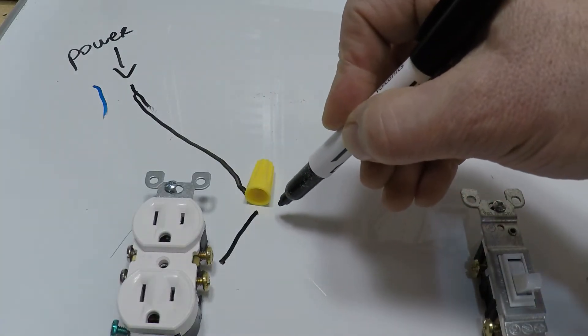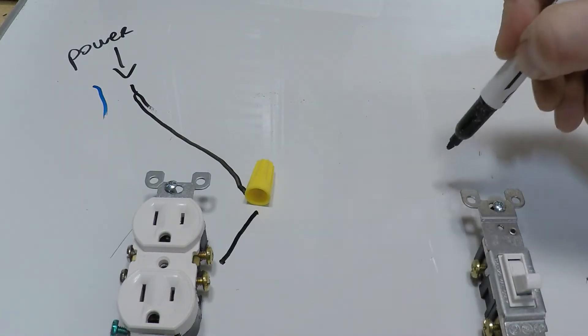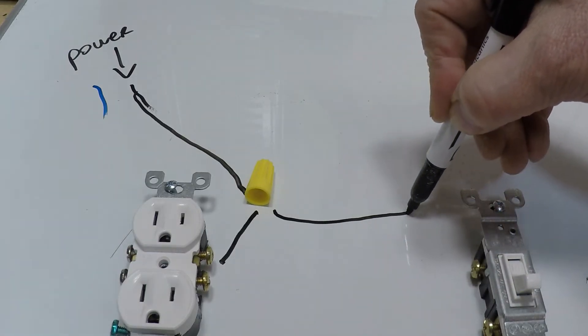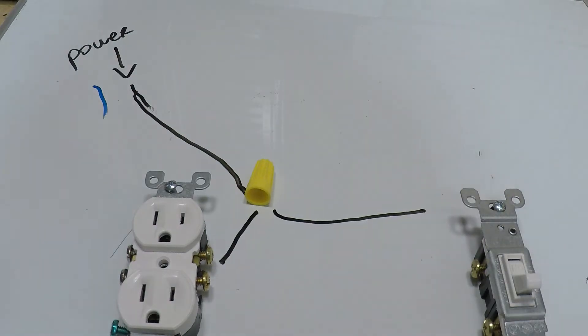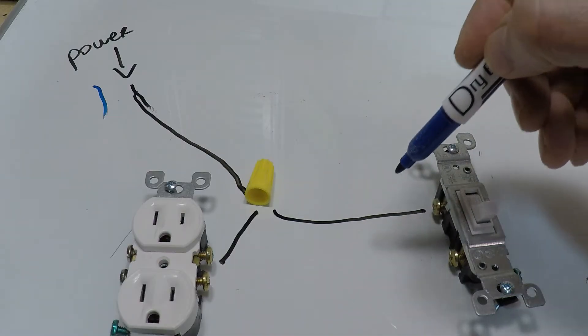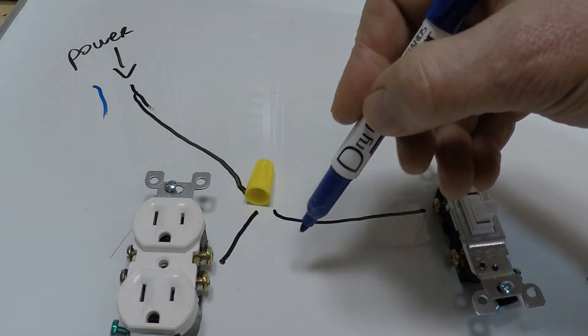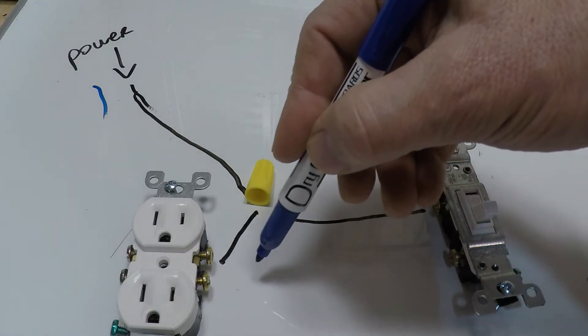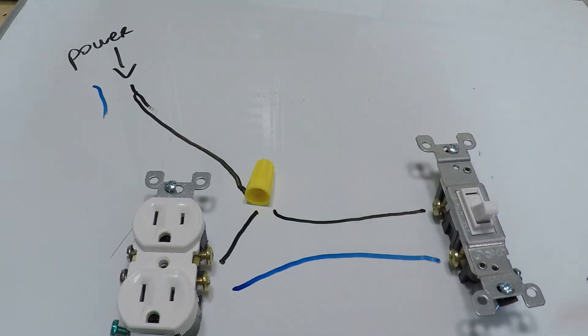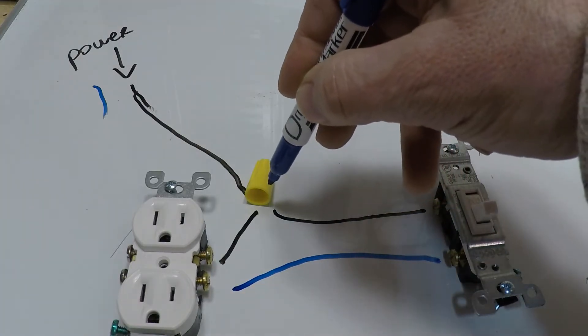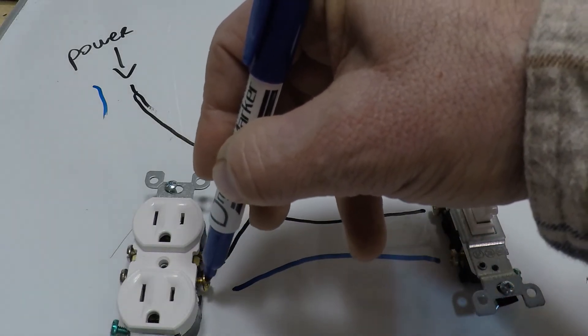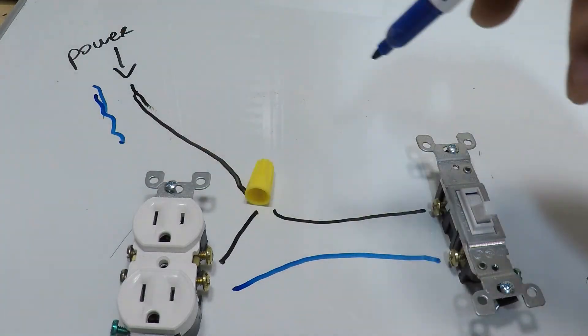And then you would have another wire going through the wall to where your light switch is, and you'd have the black—also remember it's just one wire, we can use the black wire here. And then you'll use the white of the same wire going to this screw. In both situations, this is hot coming in. You flip the light switch on, and then it's hot going back to this screw here. And over here you can have another wire nut.